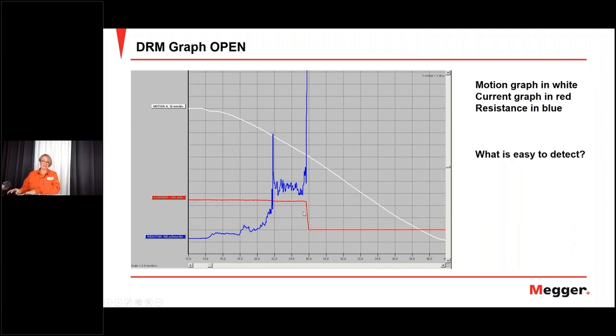So what you can see here with not so much knowledge is that the circuit breaker is opening here, because here the resistance goes to total supermax and here the current is interrupted. What's happening here? Here the circuit breaker is static. Nothing is changing, right? Here it starts to move, and then you will get a sliding of the main contact. So this part tells us information about the main contact status. And here you get the information of the last part, which is the arcing contact.